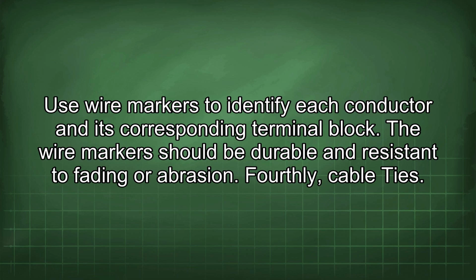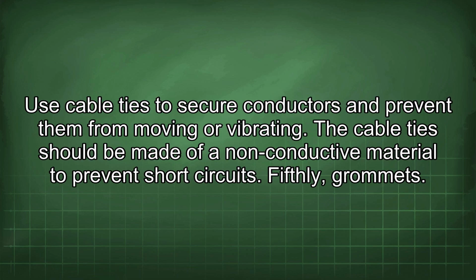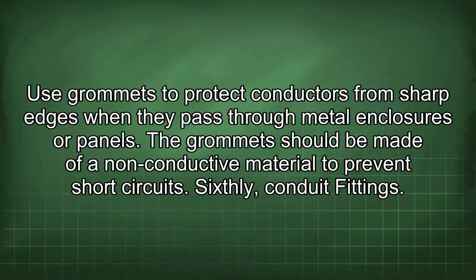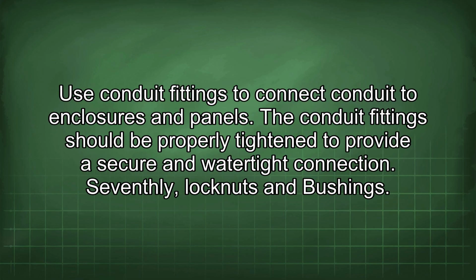Fourthly, cable ties. Use cable ties to secure conductors and prevent them from moving or vibrating. The cable ties should be made of a non-conductive material to prevent short circuits. Fifthly, grommets. Use grommets to protect conductors from sharp edges when they pass through metal enclosures or panels. The grommet should be made of a non-conductive material to prevent short circuits. Sixthly, conduit fittings. Use conduit fittings to connect conduit to enclosures and panels. The conduit fitting should be properly tightened to provide a secure and watertight connection.